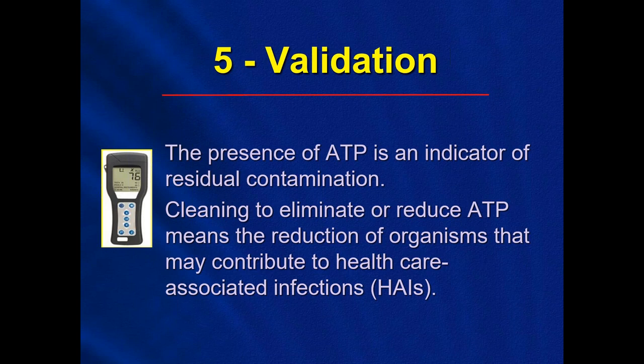So if you have a scope that was just cleaned, and it's done with the cleaning process, and you test it for ATP and you come up with a higher value than is acceptable, again, that scope would need to be cleaned again and retested to make sure that it's had a good cleaning process before sterilization or high-level disinfection.